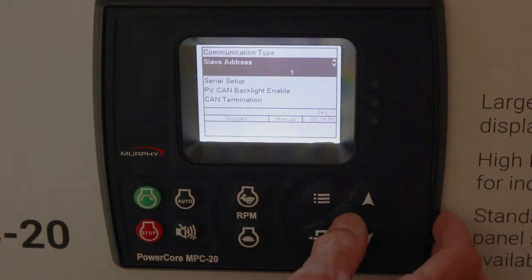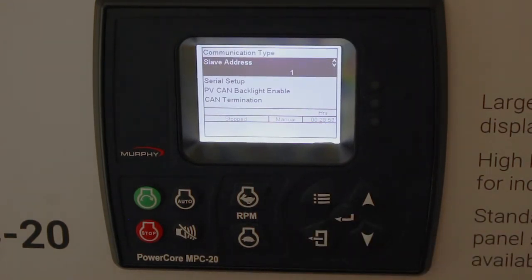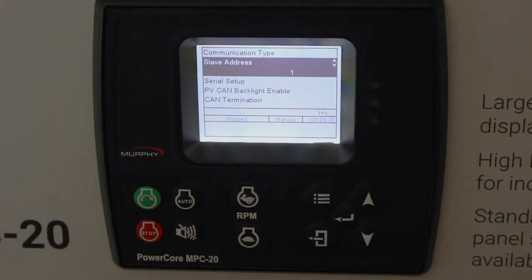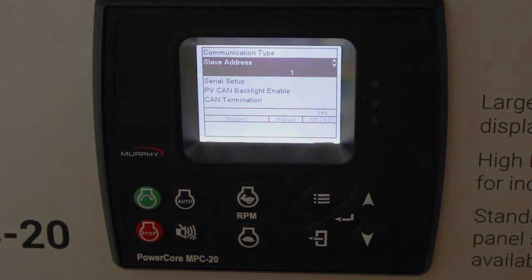The slave address for Modbus — or node number as we used to call it — defaults to 1. That way, if the folks doing the querying have a PLC in a large facility with different nodes to query, they'll assign this an address number. When a message is sent out over the RS-485, it only goes to the right recipient — we only receive messages addressed to slave address 1, or whatever address is configured here.